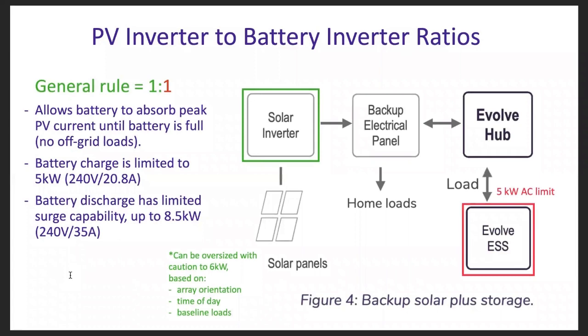And moving right along, just real quick, PV inverter to battery inverter ratios. As a general rule, it should be 1-to-1. This allows the battery to absorb peak PV current until the battery is full. And that's assuming that there are no off-grid loads. And this is also in backup mode. The battery charge is limited to 5 kW. Again, it's a 5 kW inverter. So excess PV or that charge current needs to be limited to a maximum so as to not trip the battery system offline. The battery discharge has limited surge capability up to a maximum of 8.5 kW for 5 seconds.